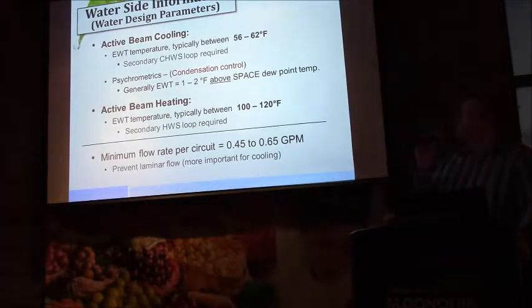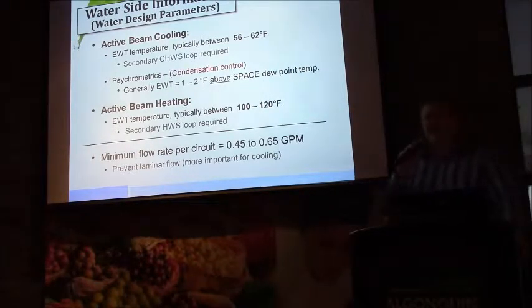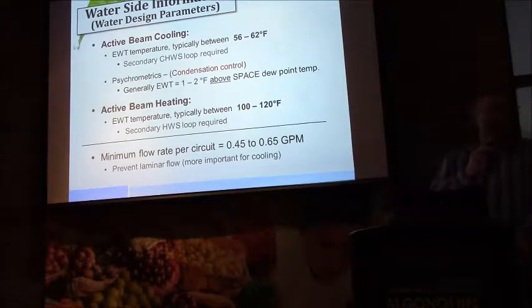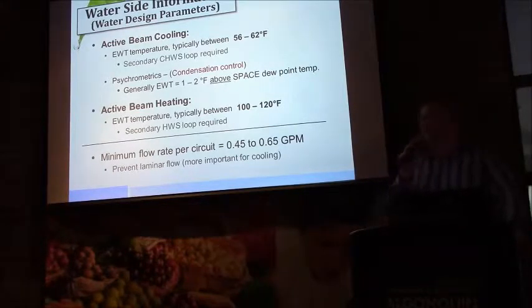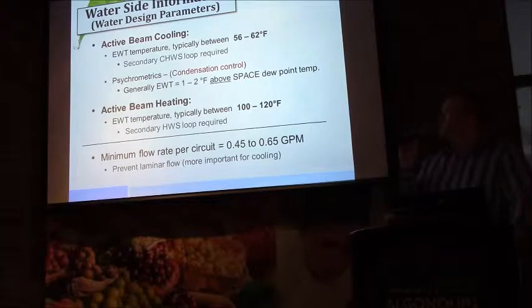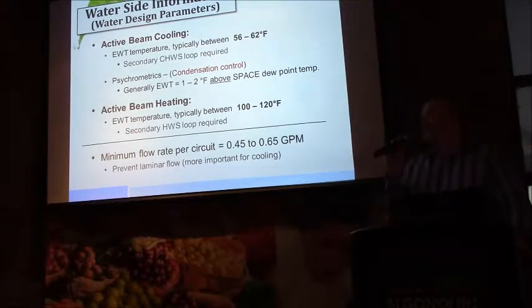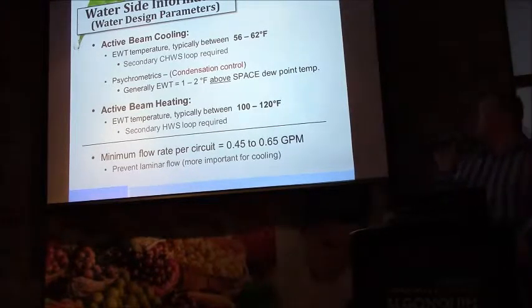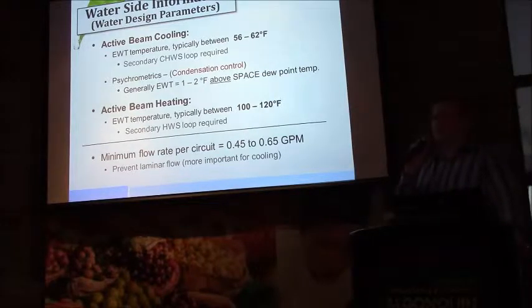relative humidity. And then, of course, in heating, overhead heating, to ensure that we have proper air movement in the space, we need to limit the discharge air temperature. And generally, that will mean that the supply water temperature to the beam for heating application is likely going to be no more than 120 degrees Fahrenheit for an 85 or so degree supply air temperature.